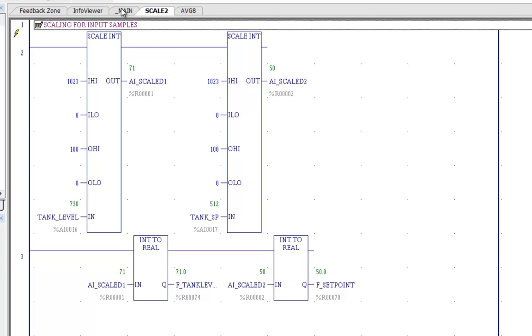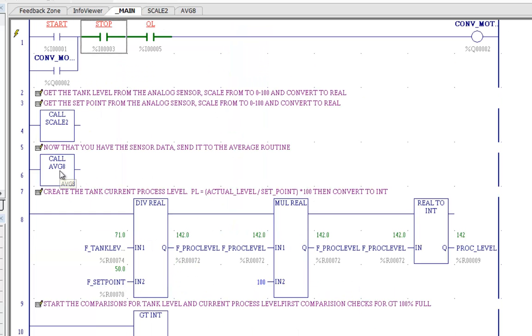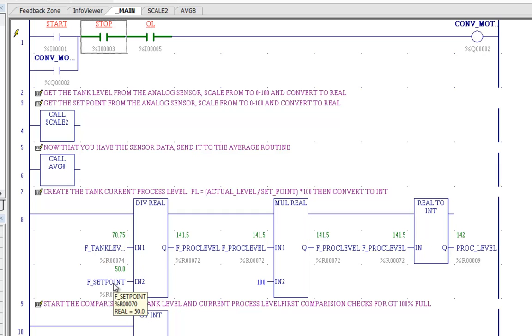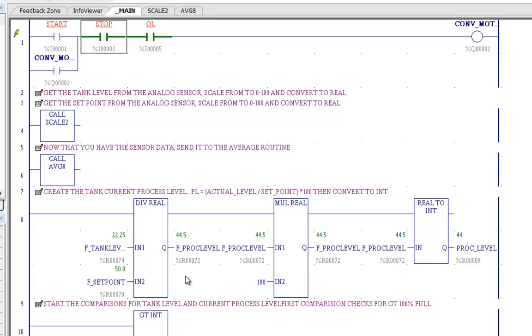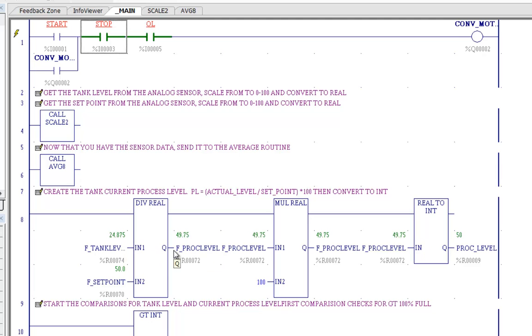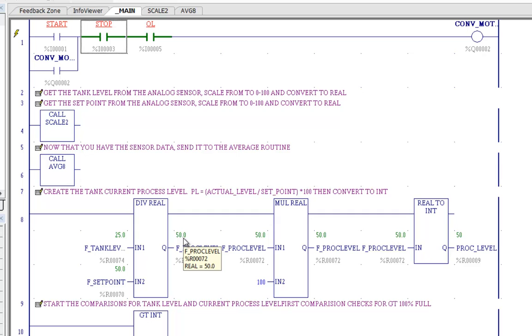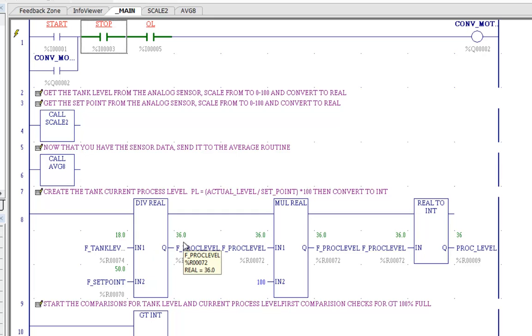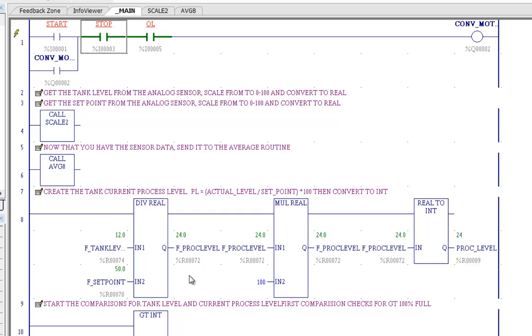Come back to our main and we go to our average we're going to skip that right now. We have our floating point tank level and our floating point set point. So this is our tank level where we're currently at. I'm going to drop that down. And our tank level is at 22. Our set point is 50. And that makes our process level about 44% full. I'm going to raise that try and get that as close as I can to 25. And you see we are now at a tank fill at 50%. If I drop this down to 12 we should be at a tank fill of 25% of our set point. There we're very close we're at 24%. So 12 and a half would get us to 25.